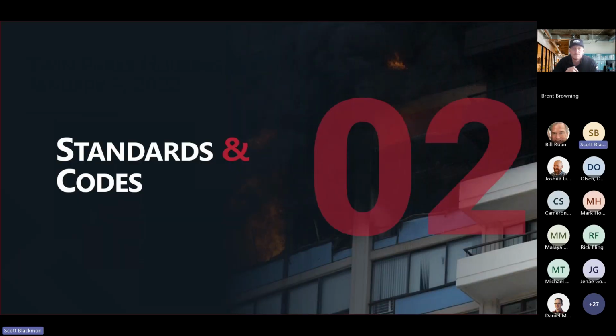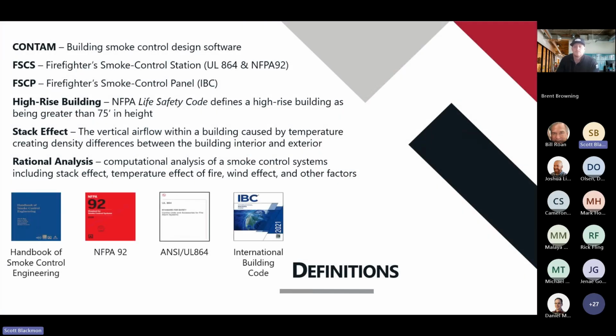When we look at codes and standards, we get those from the ASHRAE handbook, from NFPA 92, and from IBC section 909. You'll see CONTAM used in this, and that's basically the design software used to study smoke flow in a building. FSCS or FSCP, that's your fireman's smoke control station. For a high-rise building, all of this really kicks in under NFPA at 75 feet or greater. Now, a jurisdiction can lower that. So take the city of Dallas, for instance. They're at 55 feet before high-rise building code kicks in, but they usually can lower it. They don't usually raise it.